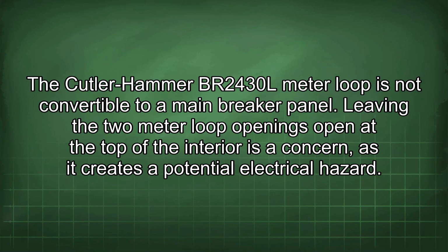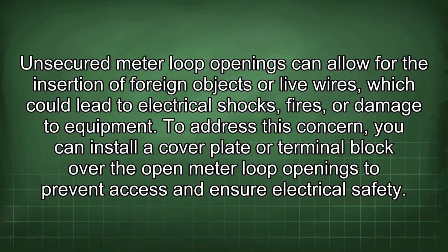The Cutler-Hammer BR2430L meter loop is not convertible to a main breaker panel. Leaving the two meter loop openings open at the top of the interior is a concern, as it creates a potential electrical hazard. Unsecured meter loop openings can allow for the insertion of foreign objects or live wires, which could lead to electrical shocks, fires, or damage to equipment.